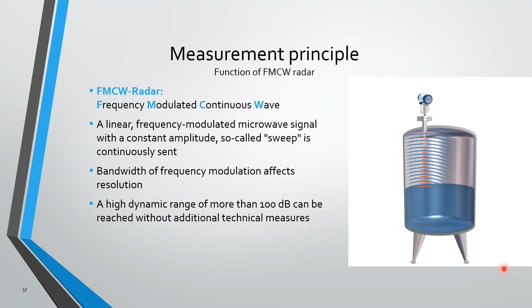So if we look at this, we have a high level there. Notice we're looking at the frequency shift, delta F, and also the time, delta T. With both of those, we're able to get a very accurate measurement, much better than we can with pulse radar. When the tank is low, you'll simply notice there's a higher shift in both the frequency and the time.